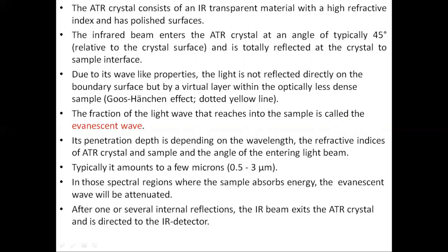Its penetration depth depends on the wavelength, the refractive indices of ATR crystal and sample, and the angle of the entering light beam. Typically, it amounts to a few microns, that is 0.5 to 3 micrometers. In those spectral regions where the sample absorbs energy, the evanescent wave will be attenuated.